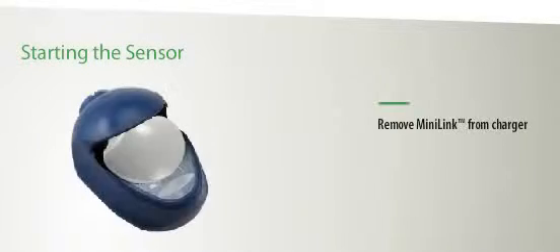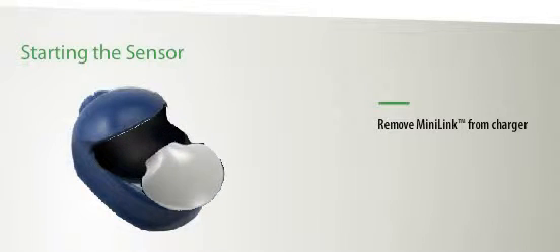First, remove the MiniLink from its charger. The green flashing light indicates that the MiniLink is charged and ready to be connected to the sensor. Next, connect the MiniLink to the sensor, making sure the sensor does not become dislodged. Once connected, the green light will flash again. This indicates that the MiniLink transmitter and sensor are ready.